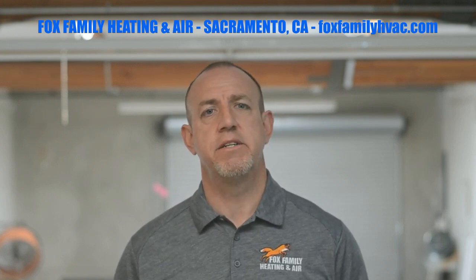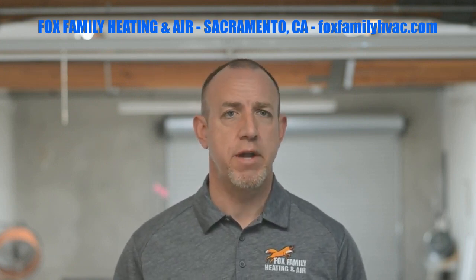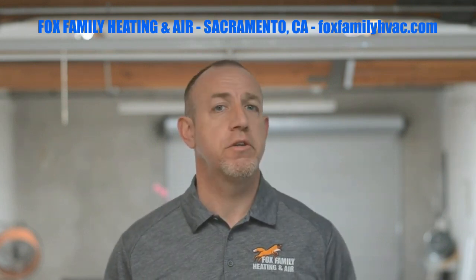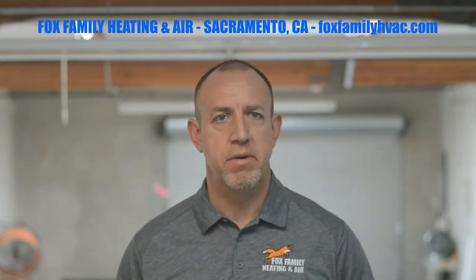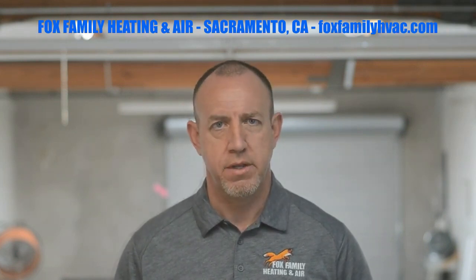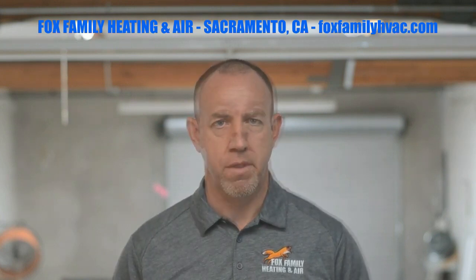When this comes up with my technicians at Fox Family, I tell them to slow down and ask themselves, why did the breaker trip? Sure, the breaker reset when you flipped it back on, but a technician finds out why it tripped. Danger. I want to reiterate that I'm only giving homeowners and technicians some ideas here as to why the breaker is tripping. I'm not advising anyone to go out and try to fix their system on their own. Working with high voltage can cause severe injury and even death to even the most experienced technicians. I read about it all the time in the mechanical chat groups that I'm in.